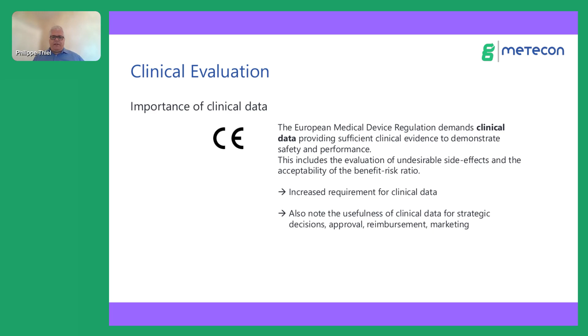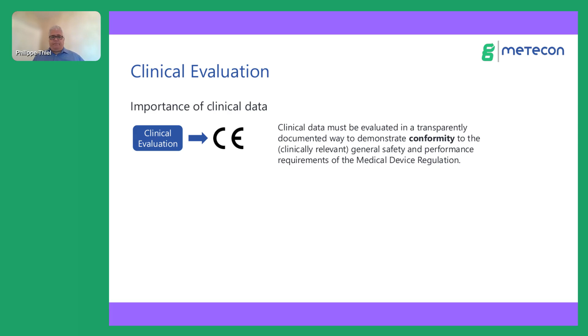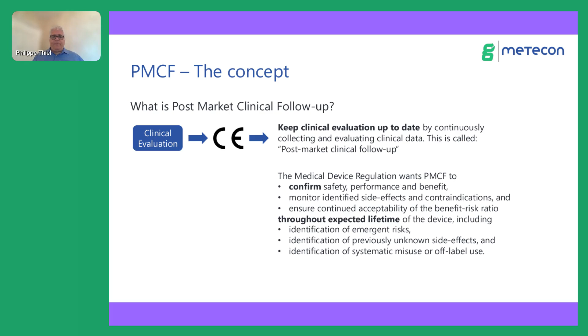So clinical data must be evaluated if you want to enter the market, and this must be documented by the clinical evaluation. A clinical evaluation is mandatory for all risk classes, including risk class 1. And after entering the market, you have to keep the clinical evaluation up to date by continuously collecting and evaluating the clinical data. That's what's called post-market clinical follow-up. And this will eventually result in an updated clinical evaluation report. So the medical device regulation wants PMCF to confirm the safety, performance and benefit. You have to monitor identified side effects and contraindications to ensure continued acceptability of the benefit-risk ratio. And you have to do this throughout the expected lifetime of the device. And you have to keep your eyes open for anything new that you haven't known before, like emergent risks, new side effects, or any kind of misuse or off-label use.